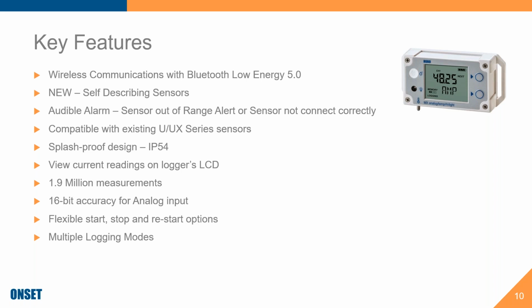There are multiple logging modes, including something called statistics, where it will record the min, max, and average over your logging interval. It runs off of 2 AA batteries, rated to run for a year at a 1-minute logging interval.